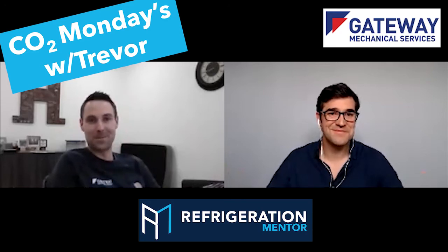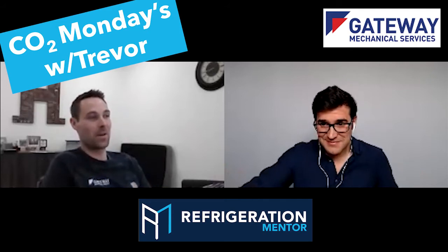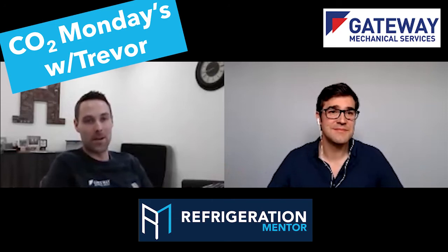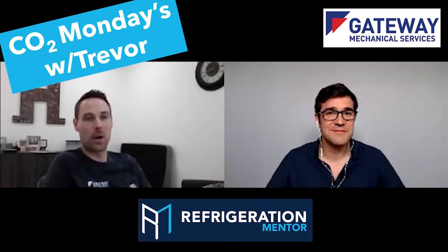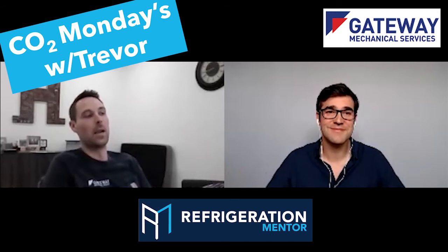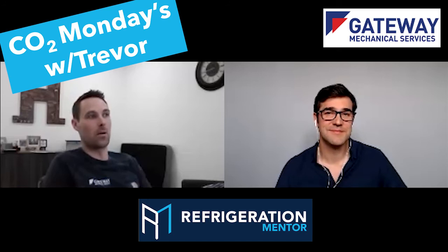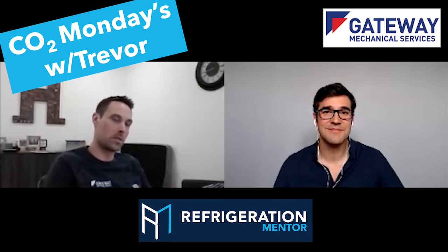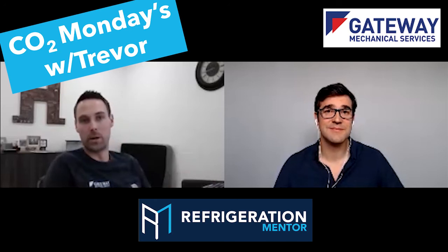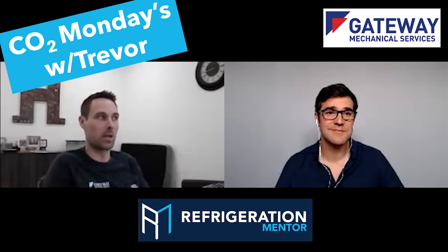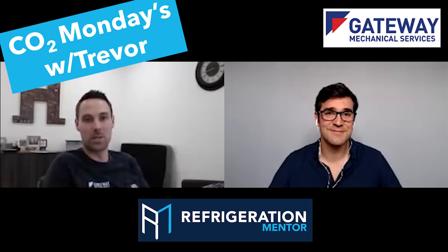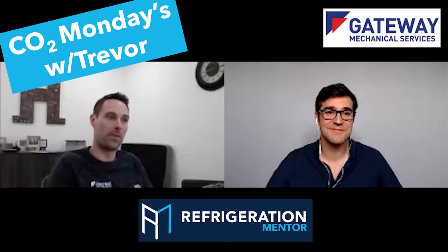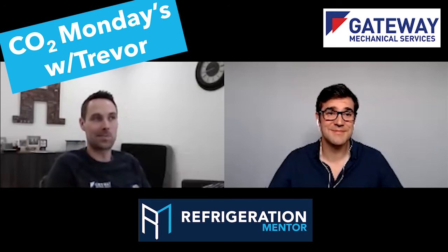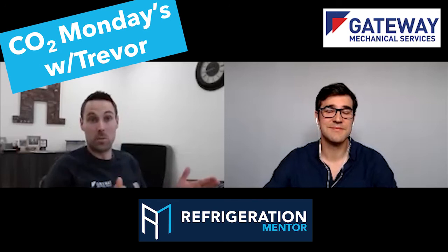Oh, I basically tell them, get familiar with it. It's not going anywhere. Yeah, fair. Usually we can talk to the rack manufacturer, and most of the time they have their base parameters they want to see, especially for the VFDs. But more importantly, is understanding why you have it, why you have a minimum hertz. Most of the time it's for motor cooling, right? You can't just let a compressor go down to 10 hertz. You're going to have motor temperature issues, and you're going to wreck that compressor. All the manufacturers I've read about have minimums, usually it's 30% or 40% kind of thing, 50% sometimes. And so you've got to really understand where those minimums are.